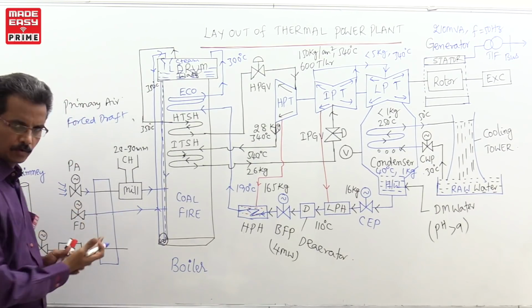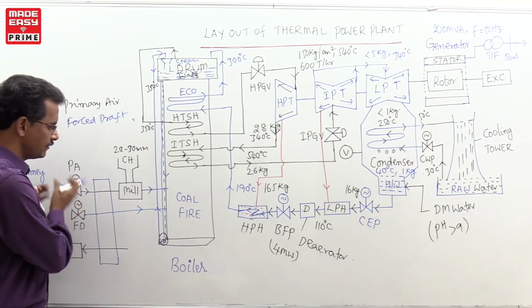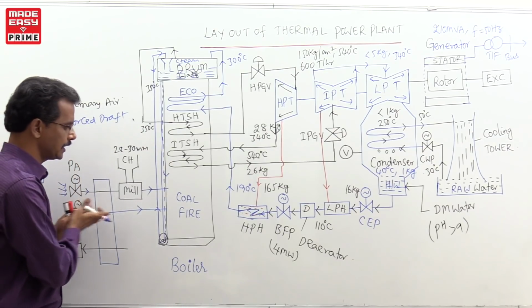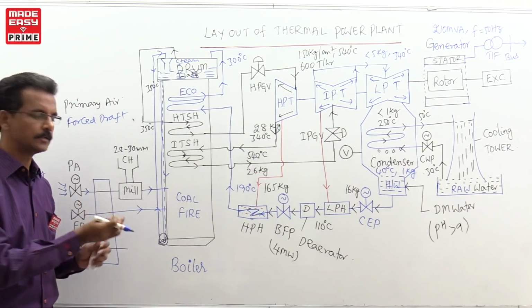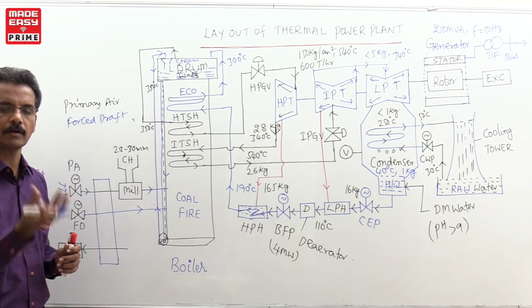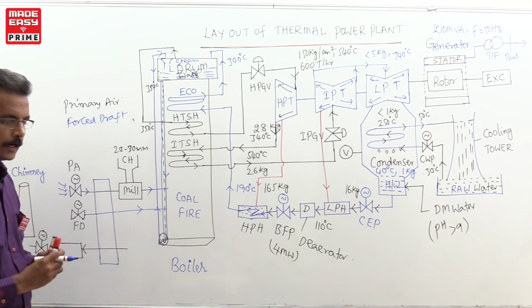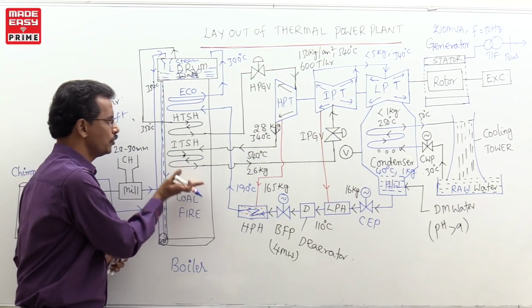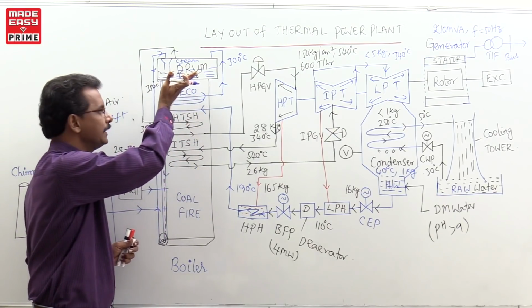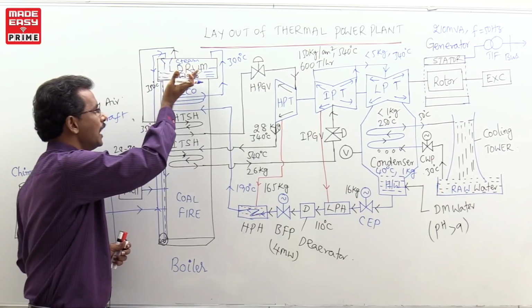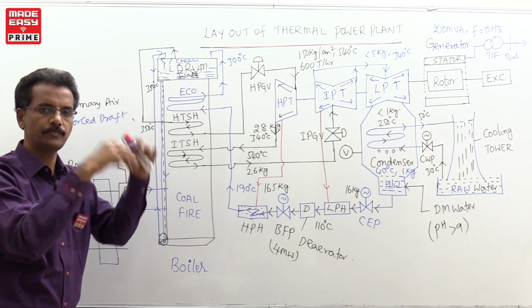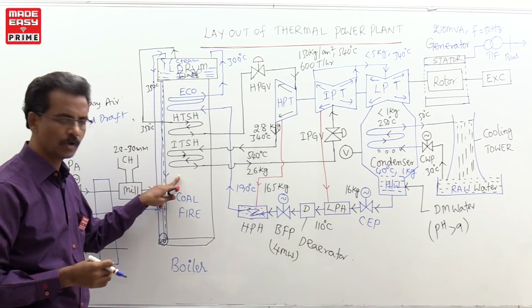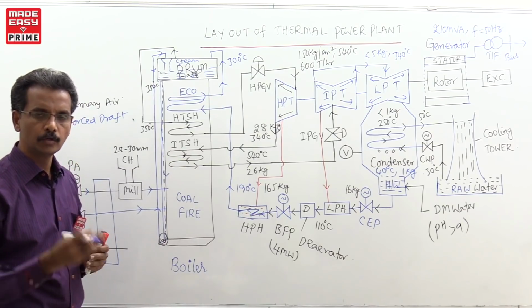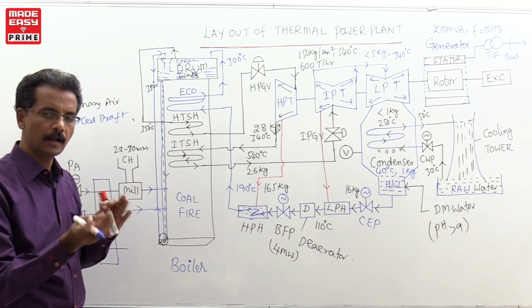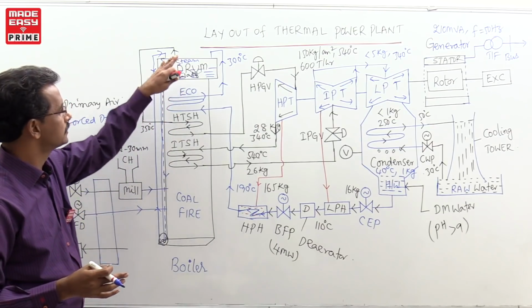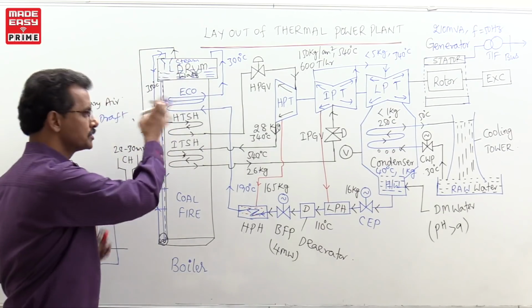The forced draft fan is actually used to supply the oxygen. It is nothing but natural air only. The fan takes the atmospheric air and pushes this air inside the boiler, so that oxygen is indirectly supplied into the boiler for proper combustion. Right. When the coal is fired, it produces flue gases, with different temperature changes, and inside the flue gas, ash particles are there. Those ash particles, along with the flue gas, we are supposed to send outside.